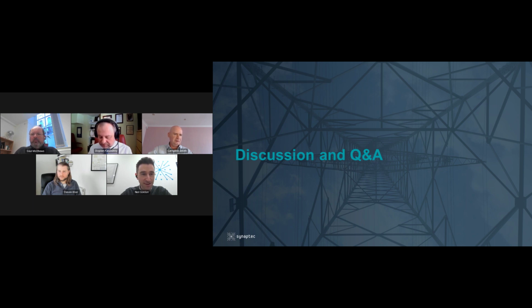Sure, I'll try and be brief. So the core technology is really the conversion of the secondary quantity, so the secondary current or the secondary voltage out of a standard CT or a VT, into an optical wavelength signal in the fiber. And that's quite different to other optical NCIT kind of Faraday effect like sensors you might have come across before, which encode the measurement in the polarization of light.